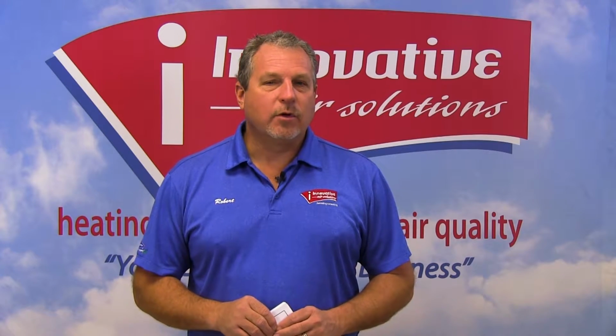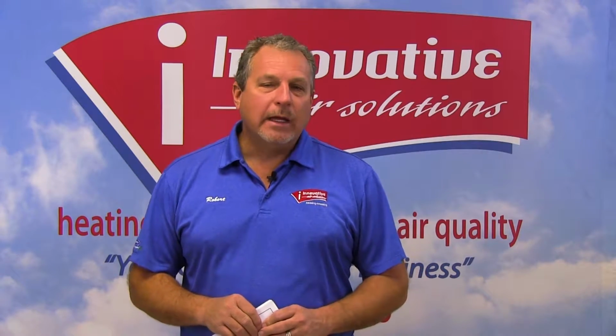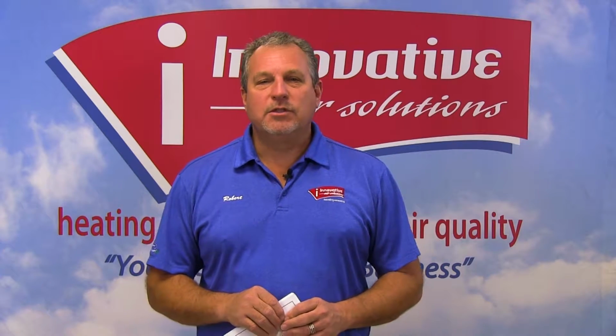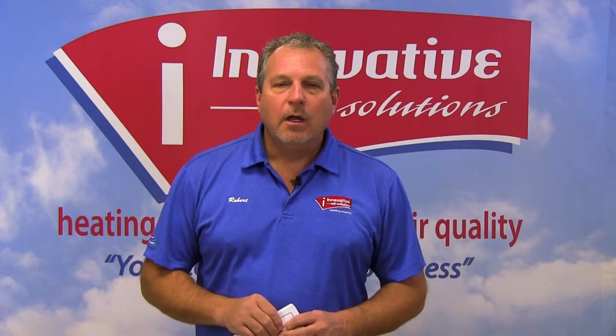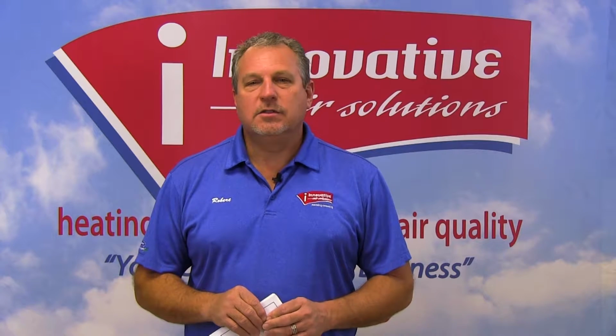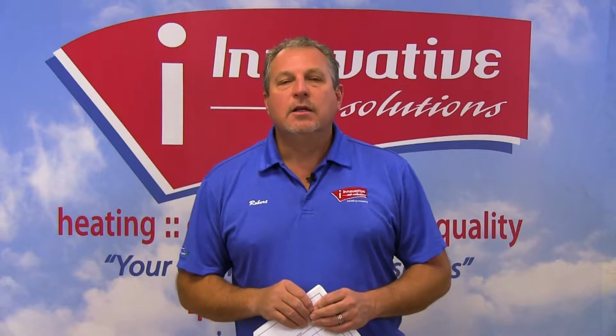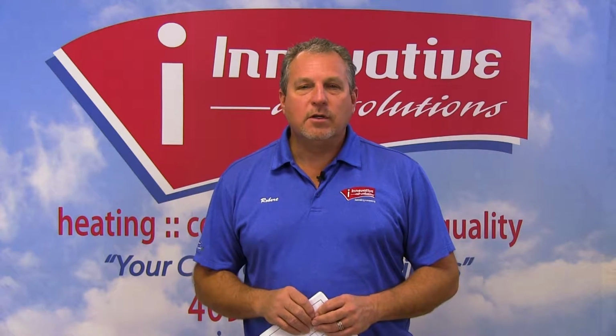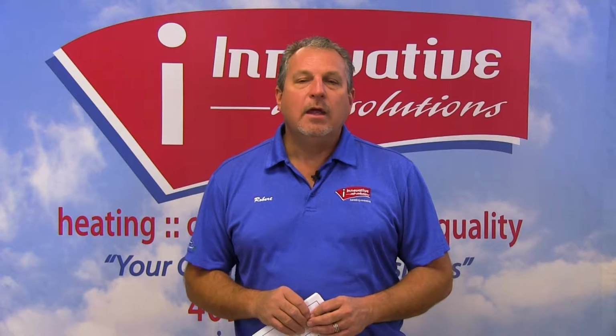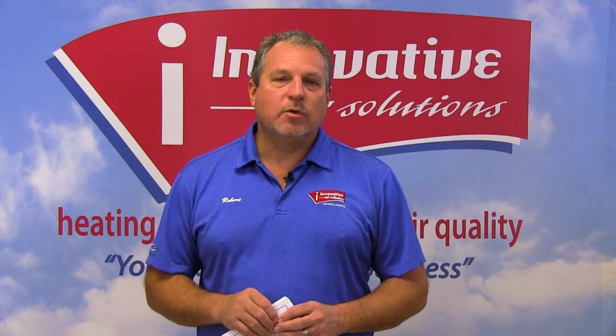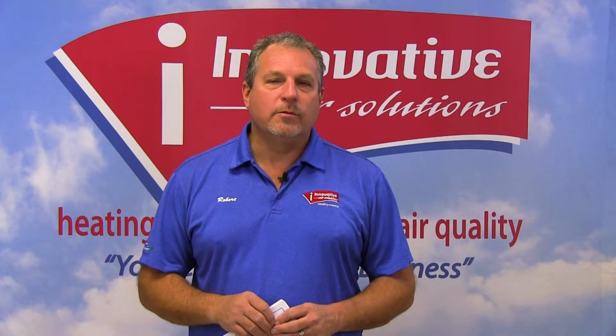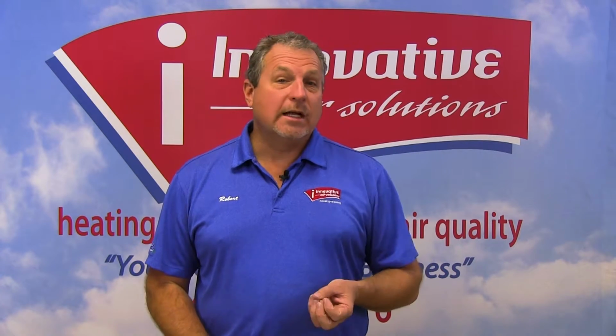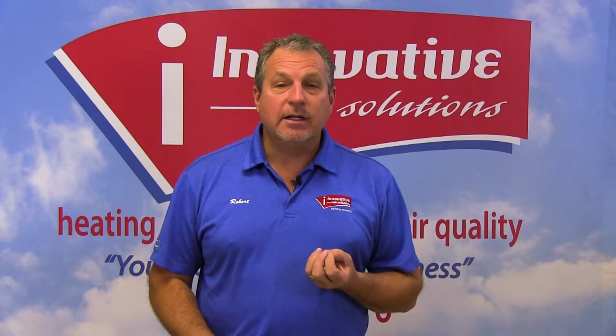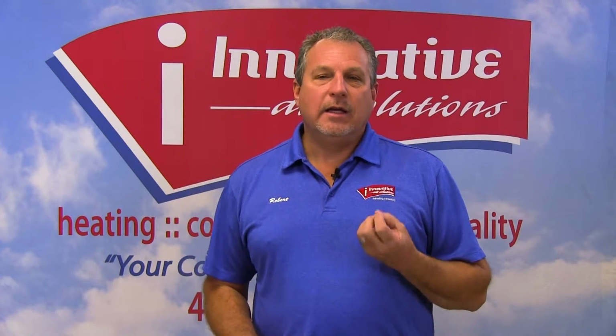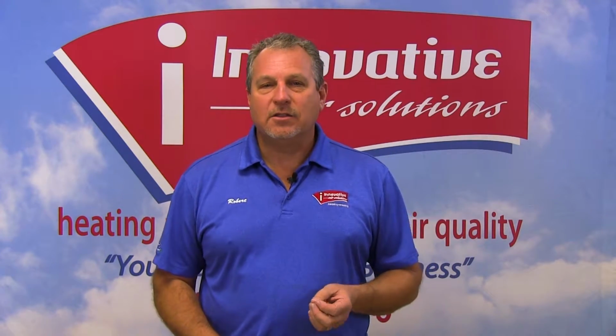They change frequently throughout the country. As an example, someone in Minnesota will design much differently than someone in South Florida, simply because of weather conditions and different seasons and things of that nature. So it's important for you to get as good of information as you possibly can. You need to be as accurate as possible when you're looking at these heat loads in order to determine what size air conditioning system we need, and how much air needs to go in each room to heat or cool it properly at design conditions.